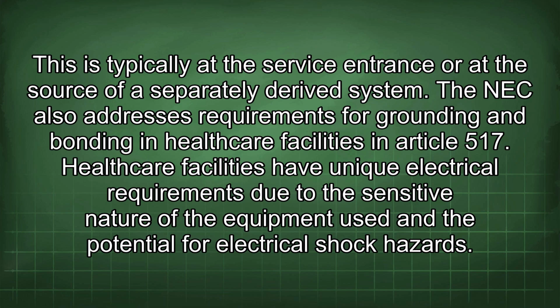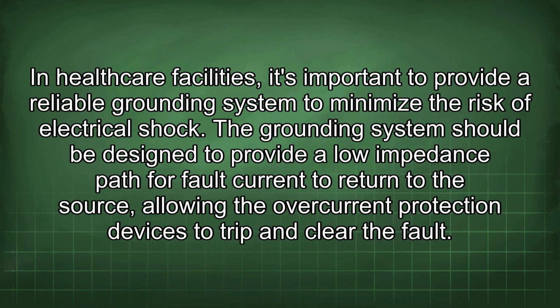The NEC also addresses requirements for grounding and bonding in healthcare facilities in Article 517. Healthcare facilities have unique electrical requirements due to the sensitive nature of the equipment used and the potential for electrical shock hazards. In healthcare facilities, it's important to provide a reliable grounding system to minimize the risk of electrical shock. The grounding system should be designed to provide a low impedance path for fault current to return to the source, allowing the overcurrent protection devices to trip and clear the fault.